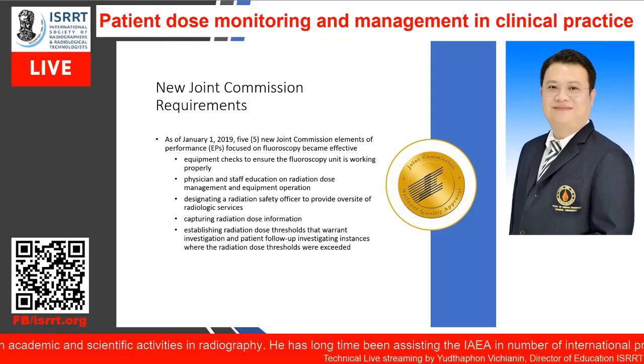In terms of interventional radiology, what you need to do to comply with the Joint Commission requirement is that the equipment needs to be checked to ensure that the fluoroscopy unit is working properly, and then you need standard staff education for your physicians who run the fluoroscopic exam on radiation dose management and equipment operation.